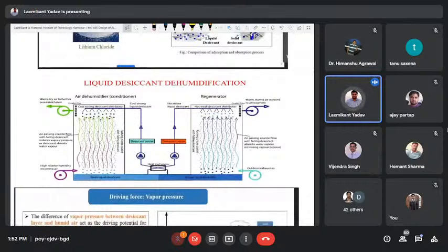Okay, so you can see the figure. There are two chambers, one called the adsorption chamber and the other called the regeneration chamber. In the adsorption chamber, dehumidification of air takes place. Hot and humid air enters from the blower below, and there is a counterflow between the spray liquid desiccant and this air. There is a fill type of structure, like in a cooling tower, to distribute the air and water evenly. So there is more contact, and more heat and mass transfer takes place.